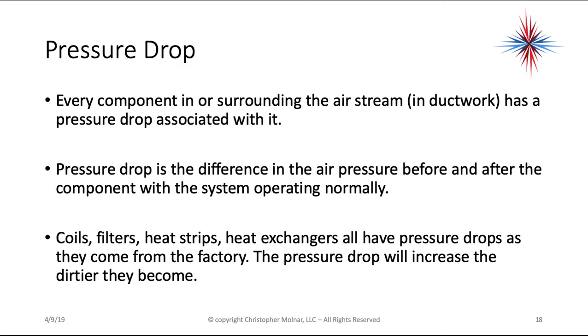Pressure drop is another term we need to discuss. Every component in or surrounding the air stream in ductwork has a pressure drop associated with it. Pressure drop is the difference in air pressure before and after the component with the system operating normally. Coils, filters, heat strips, and heat exchangers all have pressure drops as they come from the factory, and the pressure drop will increase the dirtier they become.